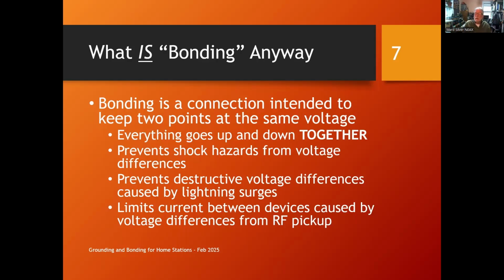If everything's bonded together and you have an insulation fault or a power cord failure or something, you don't get this piece of enclosure being at a different voltage than this piece. And when you have that happen and you touch both of them, you can get a shock. So by bonding them together, you zero out that voltage difference, and you reduce the shock hazard from voltage differences. It also prevents destructive voltage differences caused by lightning surges. When you get a big lightning transient of current, either through your station or even nearby, so that it has a strong magnetic field, what you can get is a very substantial voltage difference between these pieces of equipment. Only for a short time, but that's enough. Electricity is really, really fast. It doesn't need much time to cause current to flow.